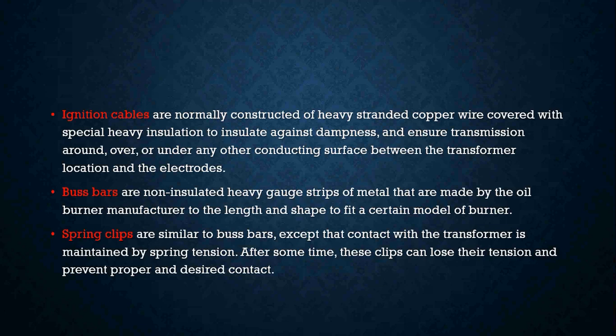Your bus bar is a non-insulated heavy gauge strip of metal made by the oil burner manufacturer to the length and shape to fit a certain model of burners. And then you have your spring clips. Those are similar to your bus bars, except contact with the transformer is maintained by spring tension, and after some time those clips can lose their tension and prevent proper and desired contact.